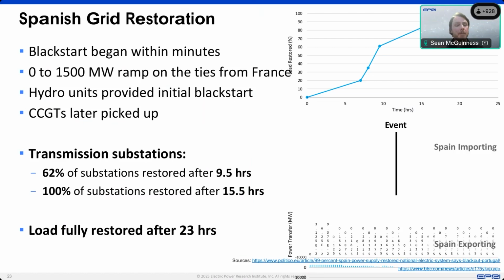In parallel with that, they brought most of their hydro units on to start energizing the grid, and after the immediate black start from the hydros, then brought in the combined cycle units and then restructured and rebuilt the grid. Black starting an entire 40 gigawatt grid from scratch is obviously not easy. It has a lot of switching actions, a lot of operators, and a lot of coordination between the system operator, distribution operators, and other significant entities and stakeholders.